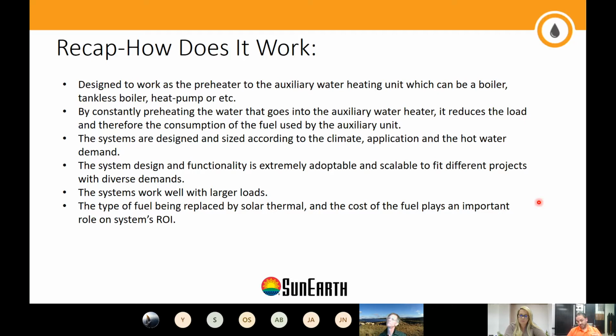But why do we need to size the auxiliary heater according to the entire load of the building? It's for the convenience and comfort of the residents, and continuous performance of the application. What if there's a week of clouds, or like we have here in California, two weeks of smoke in the sky, reducing the performance of all solar systems, PV and thermal alike? So the auxiliary system has to be sized accordingly, while the solar preheats the water, reducing the load on the auxiliary system.